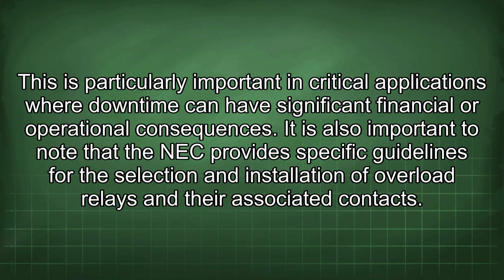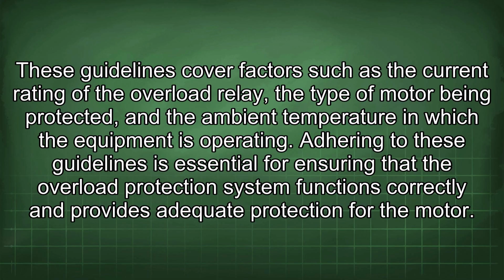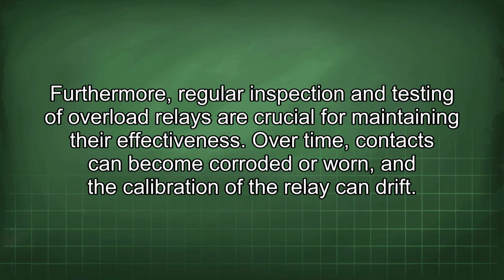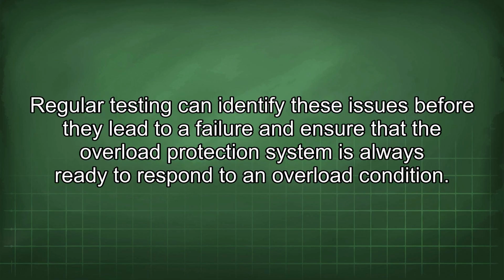It is also important to note that the NEC provides specific guidelines for the selection and installation of overload relays and their associated contacts. These guidelines cover factors such as the current rating of the overload relay, the type of motor being protected, and the ambient temperature in which the equipment is operating. Adhering to these guidelines is essential for ensuring that the overload protection system functions correctly and provides adequate protection for the motor. Furthermore, regular inspection and testing of overload relays are crucial for maintaining their effectiveness. Over time, contacts can become corroded or worn, and the calibration of the relay can drift. Regular testing can identify these issues before they lead to a failure and ensure that the overload protection system is always ready to respond to an overload condition.